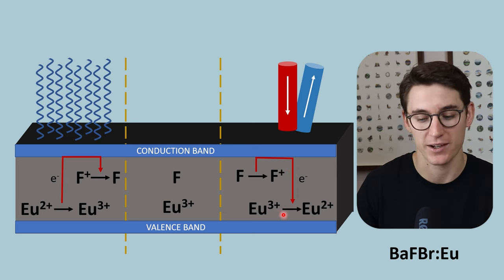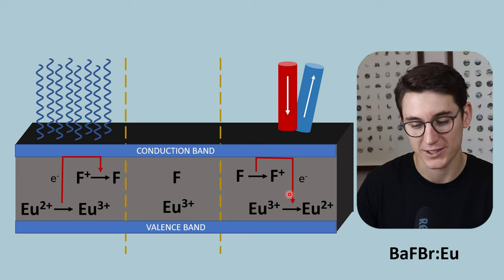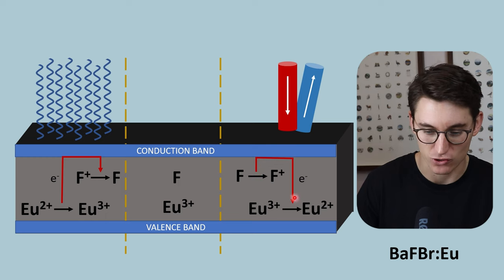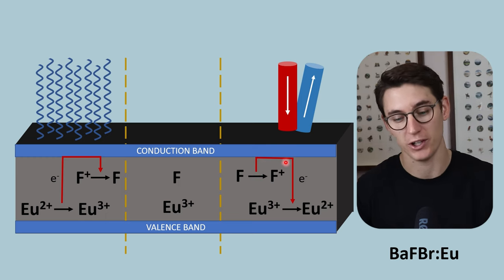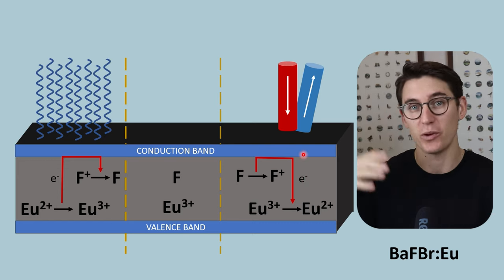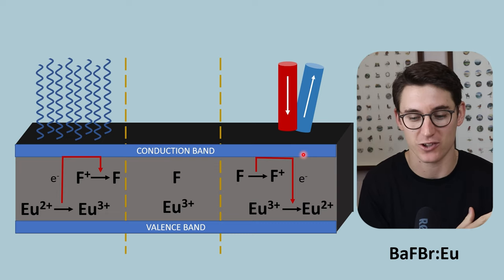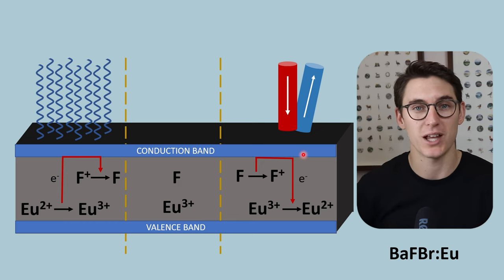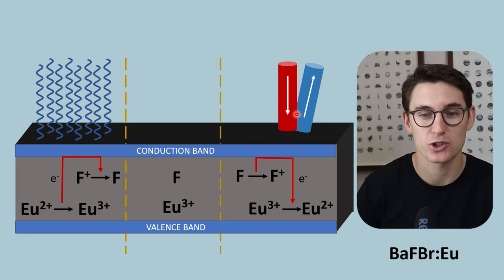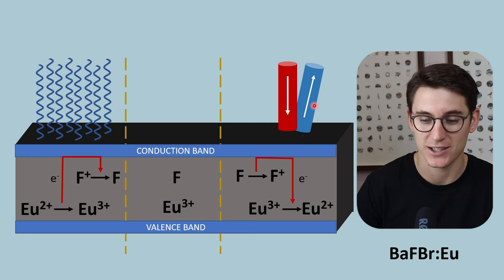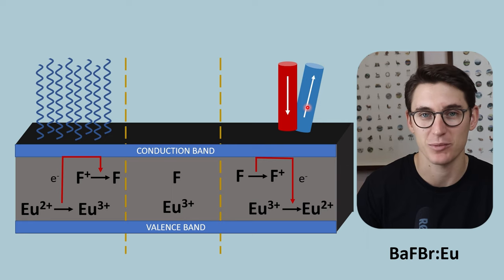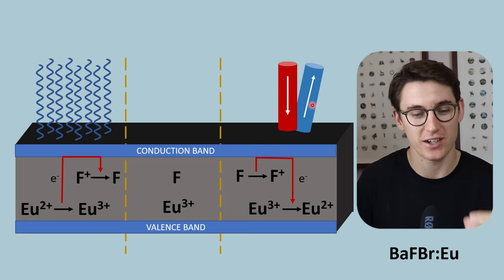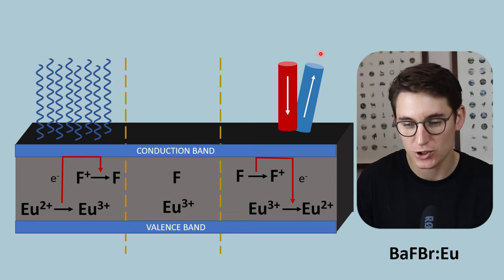That electron can then drop down into our valence band, reducing europium 3+ back to europium 2+. The electron drops from a higher energy state to a lower energy state, so electromagnetic radiation is released — and that electromagnetic radiation happens to be in the blue visible light spectrum, in the 400 to 450 nanometer range. So we shine red light onto our cassette and the release of energy occurs in the blue light spectrum. We have turned x-ray energy into light energy — a signal that is light energy.